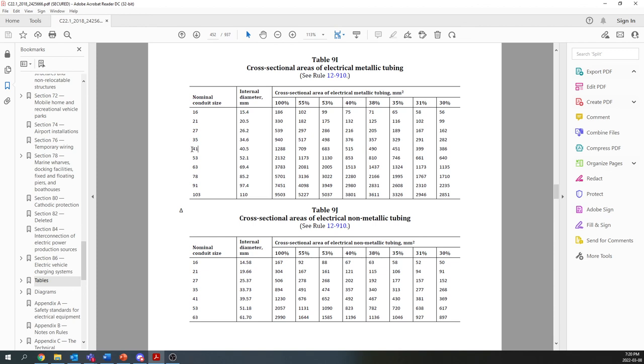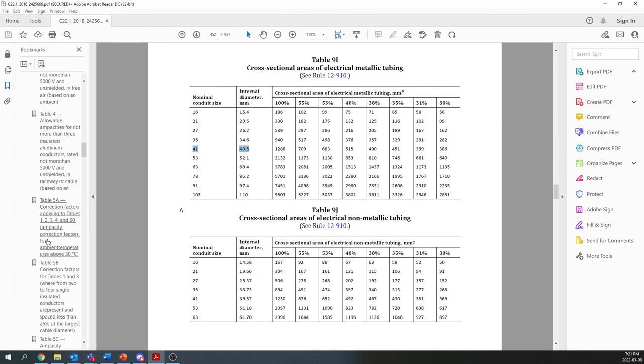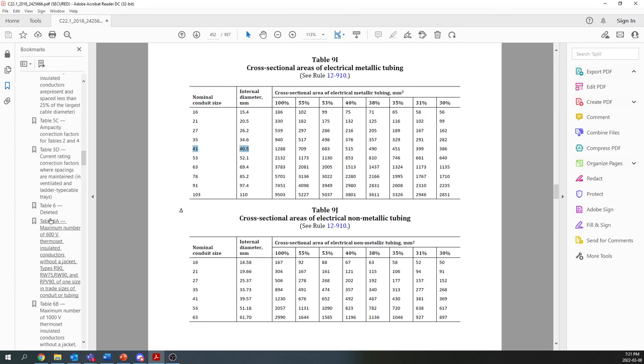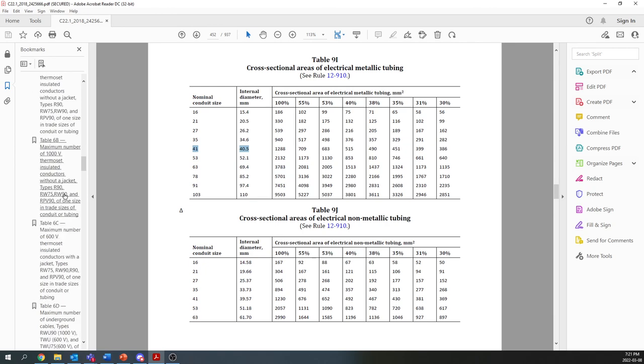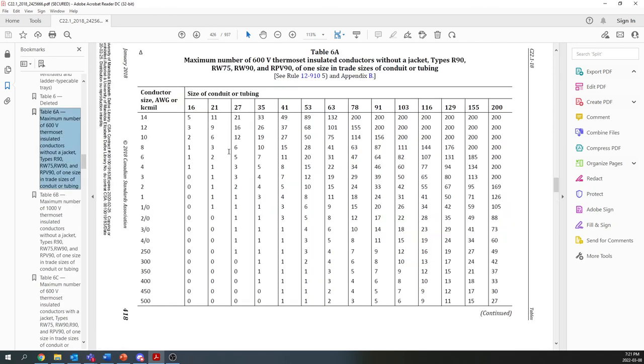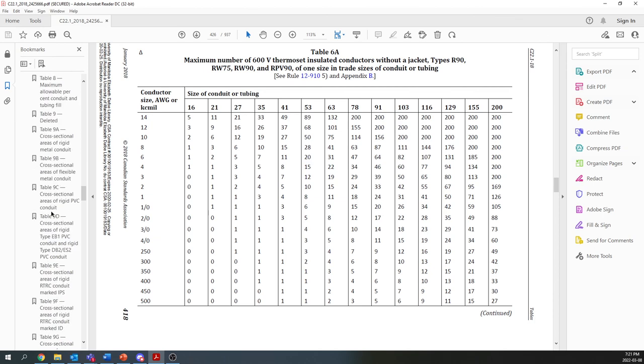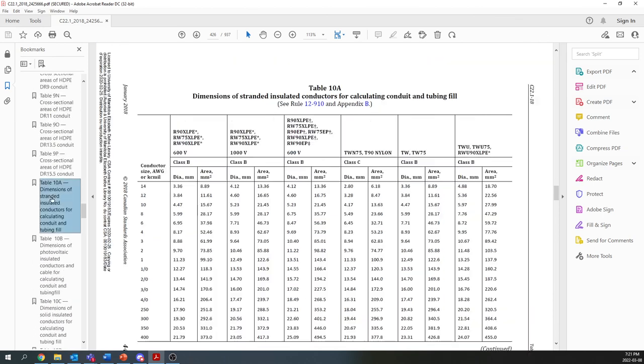So in this case, we actually saved. We're able to downsize one conduit size, because I said before, if we had assumed everything was a number 2, taking that approximation, we would have had to use a 53 conduit size. But we don't have to do that. We were actually able to go down to a 41 for the purposes of this calculation. So that's a bit of an example of how you would go about calculating your conduit size.